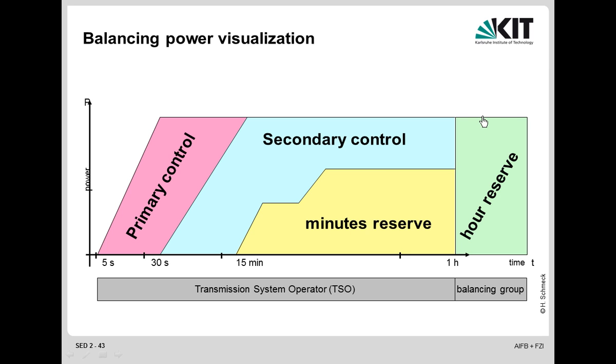This image is not completely correct. Secondary control and minute reserve can also extend a bit longer, but after 1 hour, hour reserve may take over. And hour reserve is something the balancing group is responsible for, while primary control, secondary control, and minute reserve are something the transmission system operator is responsible for. They are working on that. And so this is a cascaded scheme of balancing power.